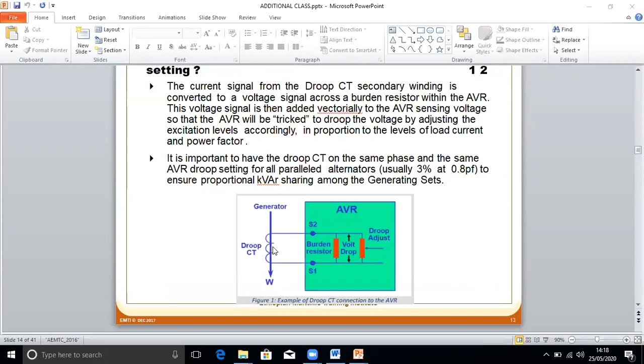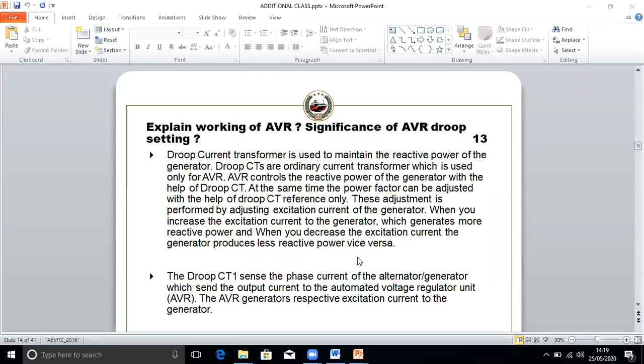Droop CTs are ordinary current transformers which are used only for the AVR. The AVR will control the reactive power of the generator with the help of the droop CT. At the same time, power factor can be adjusted with the help of the droop CT reference only. This adjustment is performed by adjusting the excitation current of the generator. When you increase the excitation current, the generator will generate more reactive power, and when you decrease the excitation current, the generator produces less reactive power.